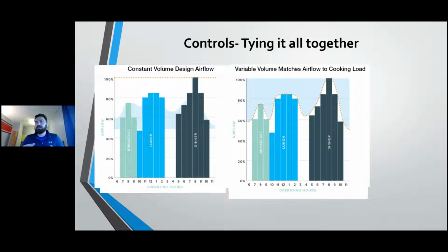What I've been seeing across the industry over the last number of years is that even in those instances that are actually lower level cooking operations, people are utilizing variable volume systems. You also hear them referred to in the market as demand controlled ventilation systems, one and the same, just depending on who you're talking to. And the reason that they'll use a variable volume system in, say, a school application is that school is never going to get to that max threshold of that temperature. That school is going to operate typically somewhere between 50% and 75% of design. So if you're thinking about that from an energy consumption standpoint, then the long-term energy savings of utilizing a variable volume system is typically going to be a good payback.